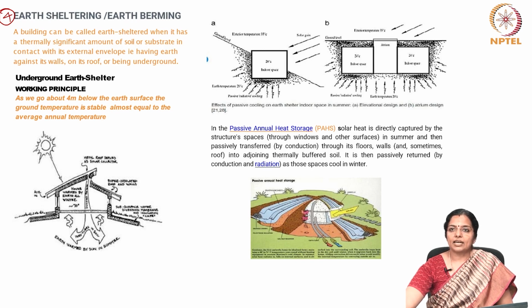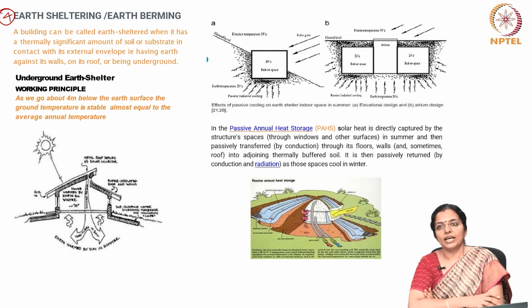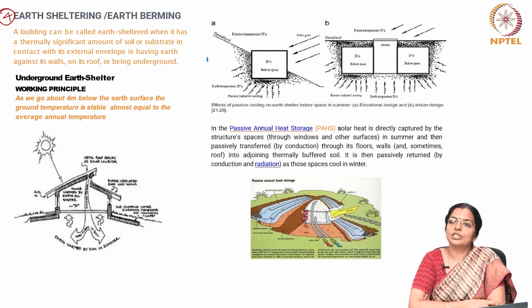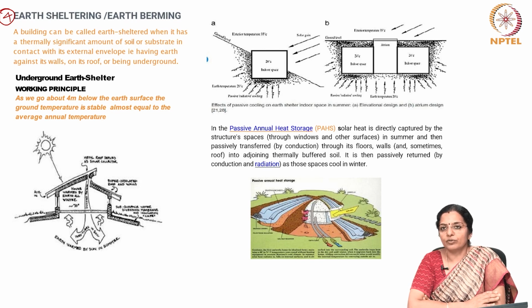Its working principle is that as we go about 4 meters below the earth's surface, the ground temperature is stable and almost equal to the average annual temperature of that place. Annualized geothermal solar or AGS uses a separate solar collector to capture the heat. The collected heat is delivered to a storage device which is soil, gravel bed or water tank, either passively by the convection of the heat transfer medium, that is air or water, or actively by pumping it. This method is usually implemented with a capacity designed for 6 months of heating.